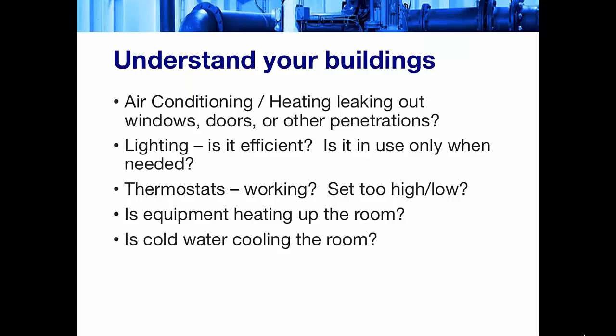Those are another place that energy can really be wasted. Not that you shouldn't use them, but you should use them wisely. So you want to understand what's causing temperature changes in your buildings. Is equipment heating it up? Is cold water cooling it down? Is the cold water in the pipe causing the condensation? What can you do to control those, and how can you use them wisely? So those are the kind of quick evaluations of your system. And we will go to the next question.